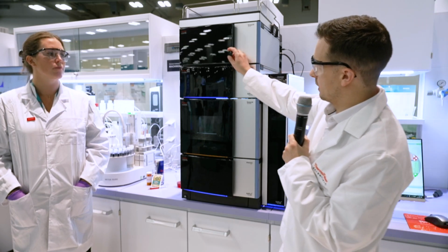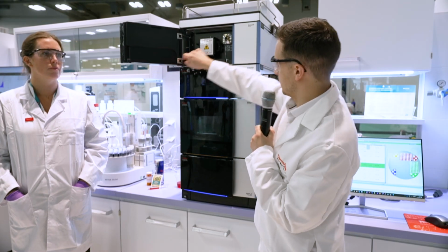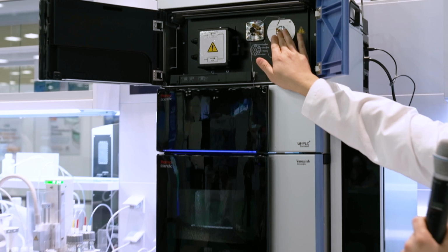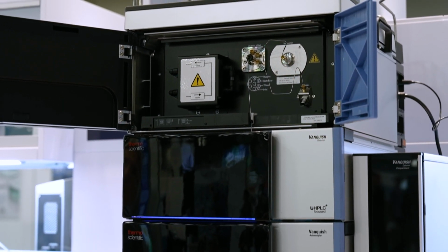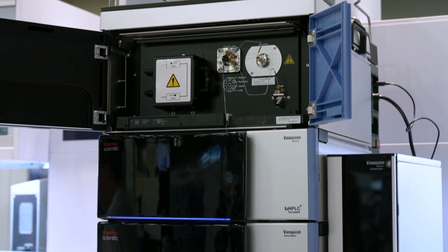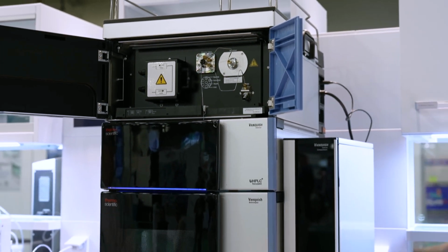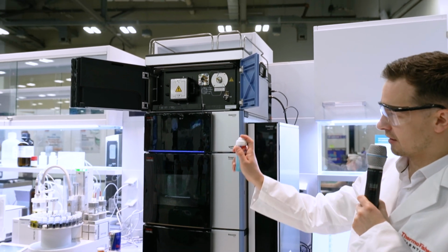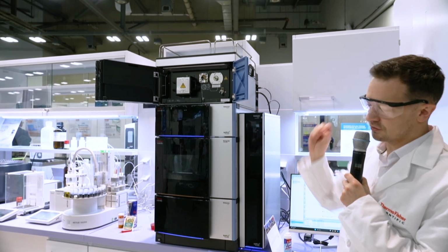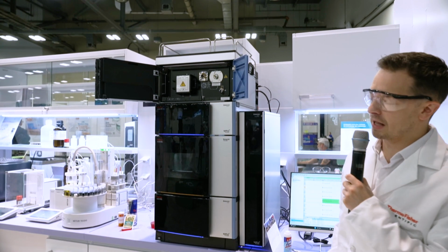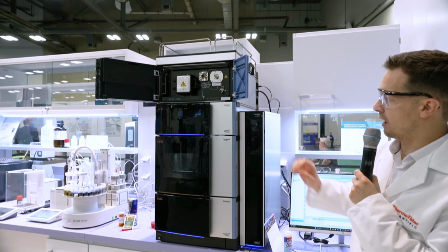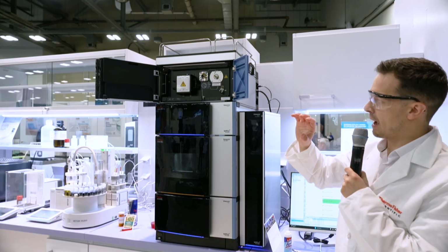And then this will flow into the charged aerosol detector here. So we've got this line that comes up, and then that feeds into the nebulizer. Now, as I said, it's a charged aerosol detector, so we're generating an aerosol. What this nebulizer is doing is basically something similar to this.